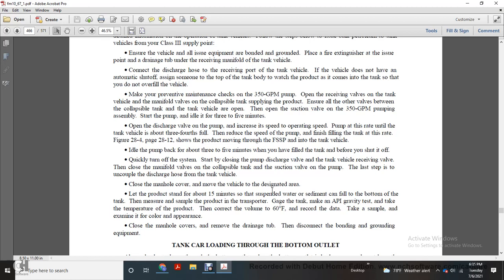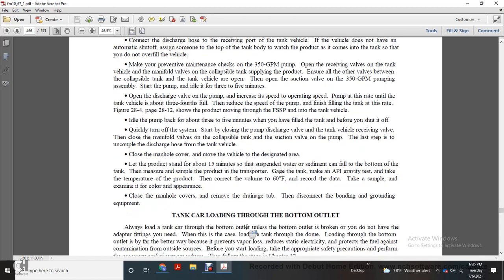From your Class III supply point into the tank vehicle, idle the pump back for about three to five minutes after you fill the tank, before you shut it off. Then quickly turn off the system. Start closing — close the pump discharge valve and the tank vehicle receiving valve, then close the manifold valve and the collapsible tank suction valve on the pump. The last step is to disconnect the discharge hose from the tank vehicle. Close the manhole, then move the vehicle to the designated area. Let the product stand for about 15 minutes to allow water and sediment to settle to the bottom of the tank. Then measure and sample the product within the transport. Gauge the tank, make an API gravity test and measure the product temperature, then correct the volume to 60 degrees Fahrenheit. Record the data, take a sample, and examine it. Close the manhole, remove the drainage tub, and disconnect the bonding and grounding of the equipment.